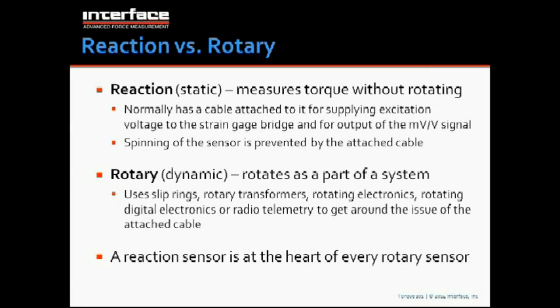Now, a rotary sensor basically takes a reaction sensor and allows it to spin. So it's exactly the same sensing technology. It's just that if it's going to spin, you have to have a way to bring the power onto the rotating shaft or rotating element, and then you have to have a way to get the signal off of the rotating element. Now, very commonly, slip rings have been used, and that's where each leg of the bridge has a ring on the rotating element, and then there's a corresponding brush that touches that ring and provides a slipping connection from the rotating element to the outside world.